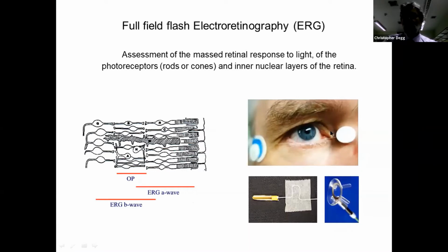Also, we can take measurements from the back of the eye to flashing lights. And we have an electrode that actually touches the front surface of the eye. So we use a silver thread, but you can also use gold foil or contact lenses with a gold lip in. We dilate the pupil for those tests, provide a stimulus, and record the signal that this detects.